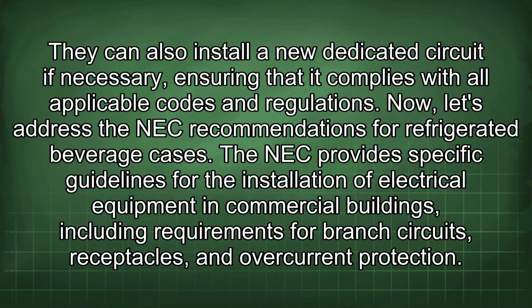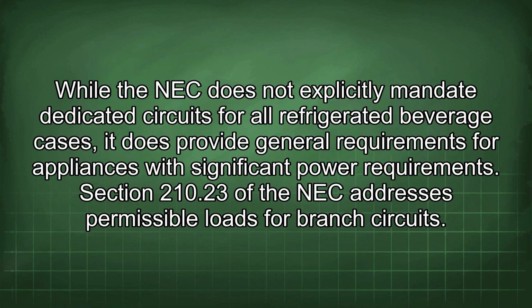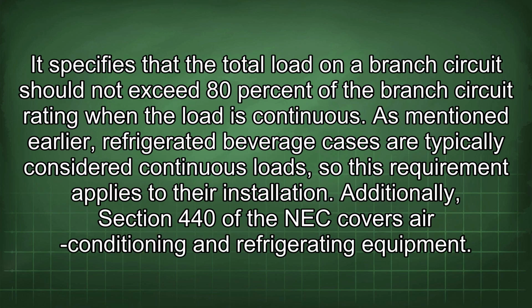The NEC provides specific guidelines for the installation of electrical equipment in commercial buildings, including requirements for branch circuits, receptacles, and overcurrent protection. While the NEC does not explicitly mandate dedicated circuits for all refrigerated beverage cases, it does provide general requirements for appliances with significant power requirements. Section 210.23 of the NEC addresses permissible loads for branch circuits. It specifies that the total load on a branch circuit should not exceed 80% of the branch circuit rating when the load is continuous.